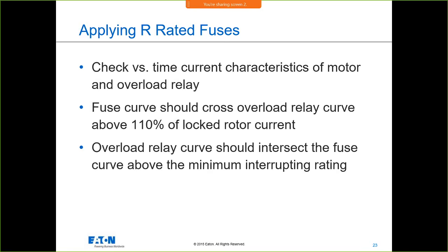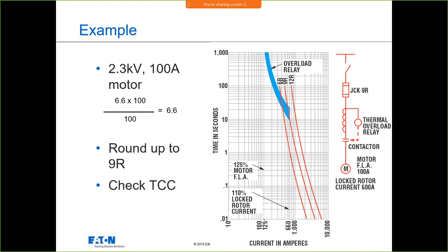But you're going to want to check the TCC curve against your motor. You're going to want to look at the fuse curve with regard to the overload relay or whatever overload device you have in that picture. And it has to intersect the fuse above that minimum interrupting rating. So this is the overlay that you want to do on these fuses for medium voltage. You could do your 2.3 kV 100 amp versus a motor. You multiply that, divide that, you get 6.6. That gets you an R rating of where you need to be.